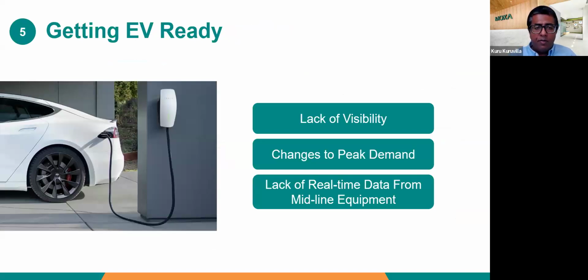Another topic is electric vehicles, which add an additional factor on the load side because of all the charging that may happen on a residential scale. Utilities typically don't have direct visibility into those individual chargers, so from a planning and operations perspective they have to make judgments. Even at the edge of the grid owned by the utility, sensing may be sporadic, so there may not be enough real-time information to use.